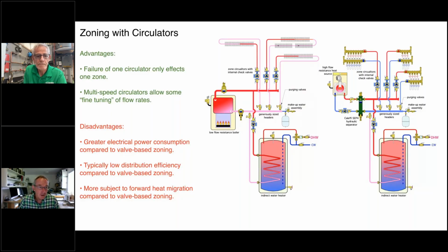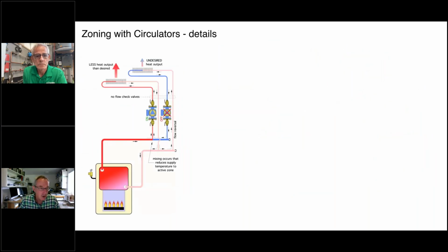So just a couple details. I mentioned it is important that you've got check valves, and just to show what happens if you don't have check valves in each circuit, here we've got a circulator that's on, and over on to its right when it's off. So normally we'd follow the flow up through the circulator through this zone, and it comes down to here. And we'd like to think that the water is intelligent, that it knows it's supposed to go back through the boiler, get reheated, come back up. And some of it will. But also some of it is going to go this way.